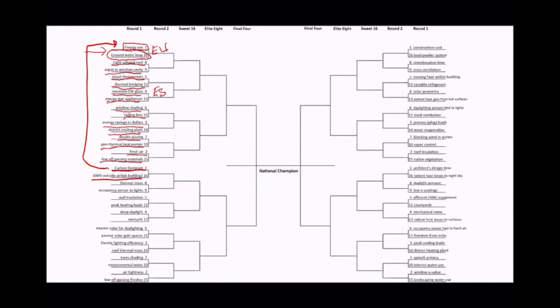Instead, we exhaust all the air from each lab space and bring in new air. That's why lab buildings use just about as much energy per square foot as any type of building. Then we start to talk about chilled beams, really smart fume hoods, radiators in the winter, and all kinds of ways to minimize the need for recirculated air. So typically carbon footprint would advance, but if we were a lab building, the 100% outdoor air would upset it - a number 16 seed upsetting a number one seed.